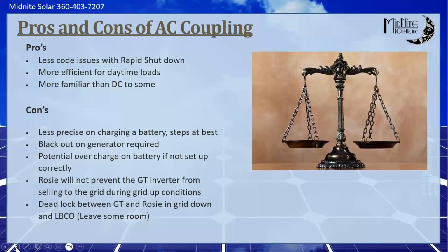Another big one is it's much more efficient for daytime loads. So if you have a building, let's say a doctor's office or some kind of manufacturing facility, and you're going to put a bunch of PV on there, having some AC coupled is nice because that doesn't get converted to DC and then back to AC. The loads come out of it first before it actually gets to the battery-based inverter.